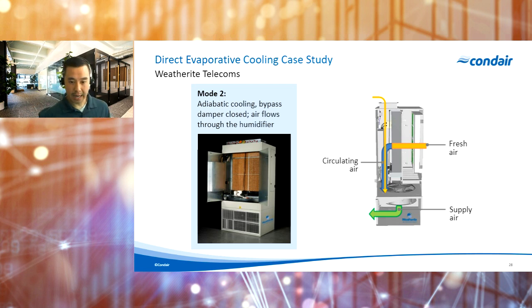Now, if you look at the unit itself, inside the cabinet here, you can see kind of a brown material. That is our glass fiber media that is installed in a full recirculating evaporative module and would come into play when we look at mode 2. Mode 2 would activate when the demand cannot be satisfied using outside air only. In this case, we would turn on the evaporative cooler and pass air through that system.